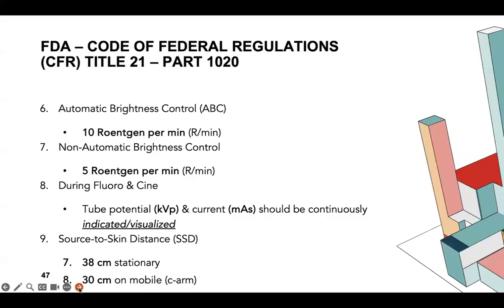That when we're using fluoro and cine on our fluoro machines, our tube potential, our kVp, and our current, our mA, should be continuously indicated and visualized. So it tells us that on the machine, we should be able to see our technique if we're using fluoro and cine functions on our fluoro machines. And that our source to skin distance, our SSD, with our stationary equipment in our rooms should be at least 38 centimeters, and with our mobile C-arm, it should be 30 centimeters.